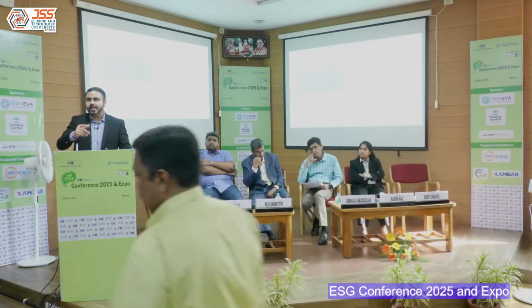So the idea was that if there are 10 compressors running, what is the best? Maybe if there are any electrical or mechanical engineers here, you would know that any equipment has a best optimal loading point at which the best efficiency is achieved. So if there are 10 compressors running, the best optimal efficiency point of all the compressors will vary as per their design, and in general it goes to around 70 to 80%. So how can you have the most optimal sharing of load across various compressors and equipment? That's what we were doing with this whole piece of smart optimization, so that you have the best efficiency coming into the picture.